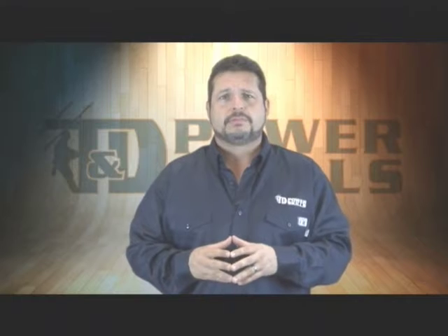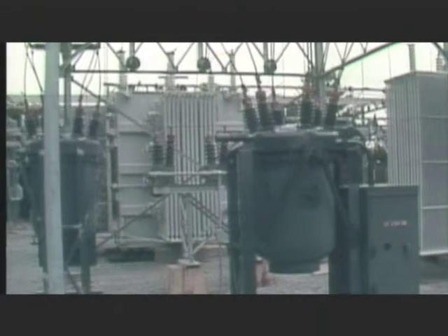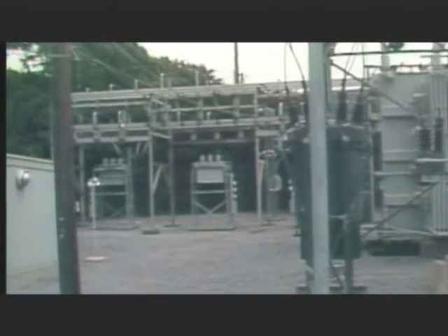from damage. Sometimes, circuit breakers are used to perform the same type of protective function, but unlike reclosers, circuit breakers are not equipped to directly monitor conditions elsewhere in the system. For circuit protection, they have to depend on signals sent by external equipment. Often, the sensing elements and control equipment are contained in a small building on the substation grounds.